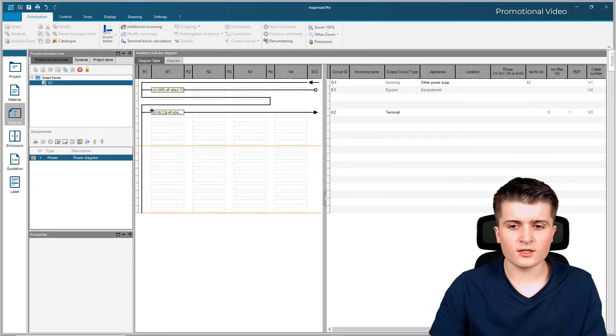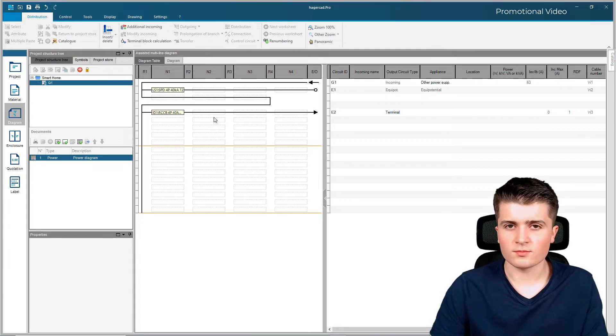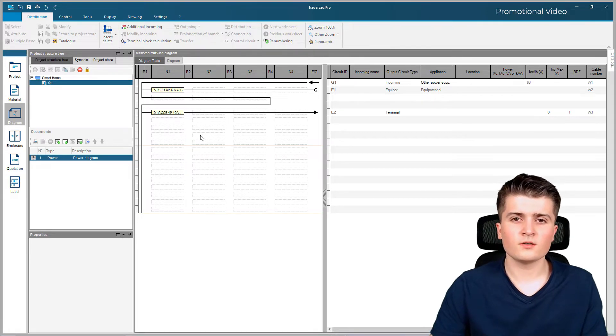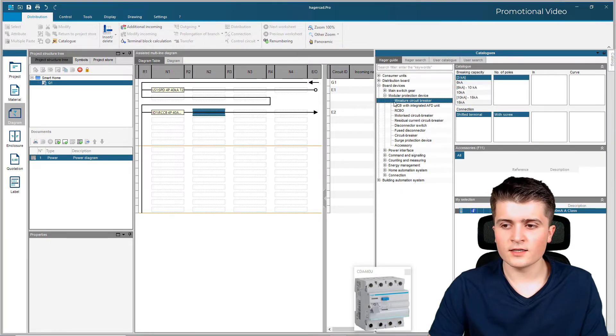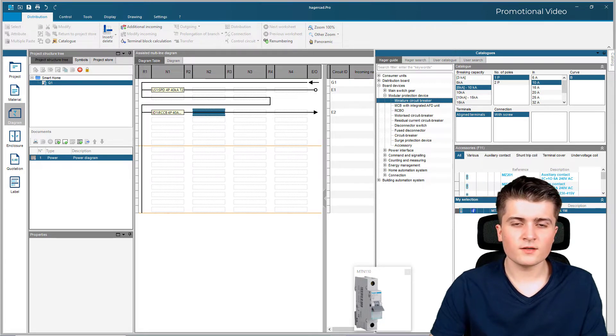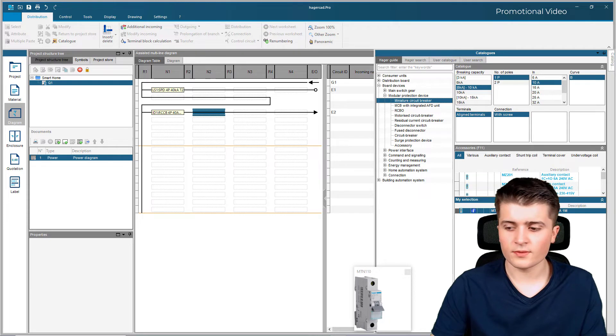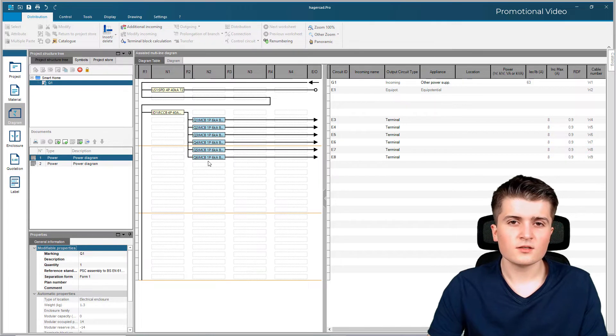We now have one RCD, which is currently directly connected to a circuit — you can see 'terminal' — but we want to add six circuit breakers in between. I click on this field, go to catalogs, select miniature circuit breaker, and specify 10 amps. Down below I can specify the quantity of devices to add, so I set it to six, then click the add symbol. With that we created six circuit breakers at the same time.